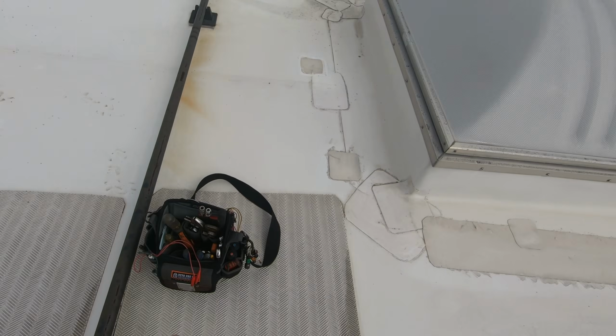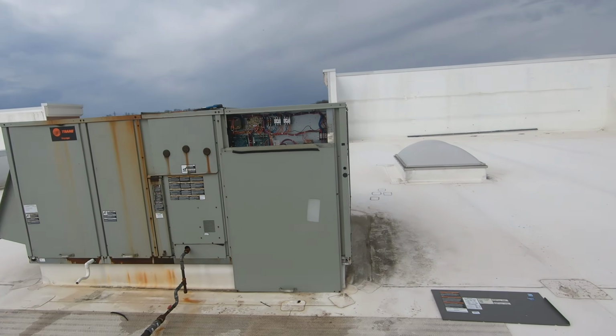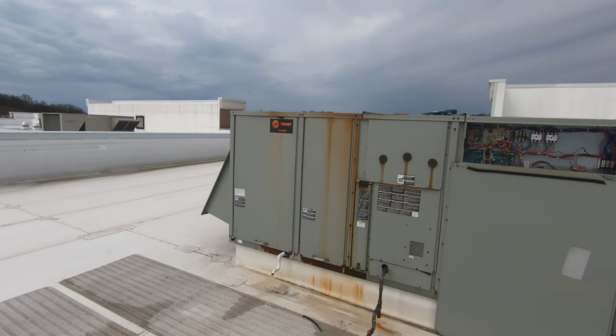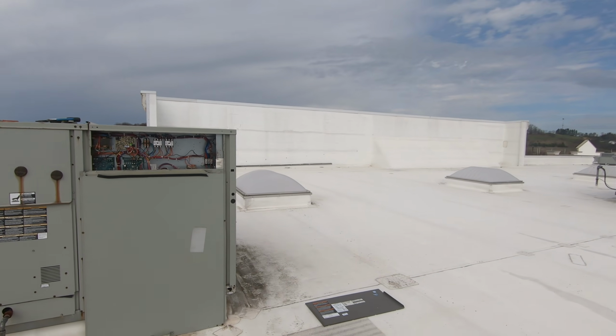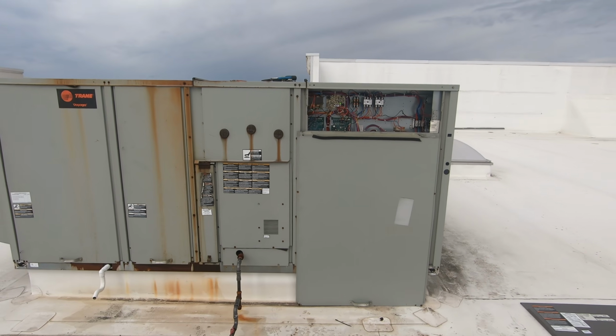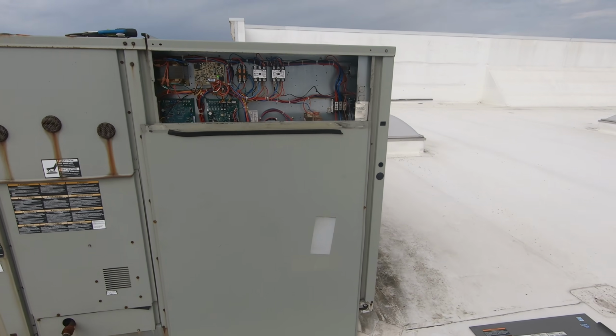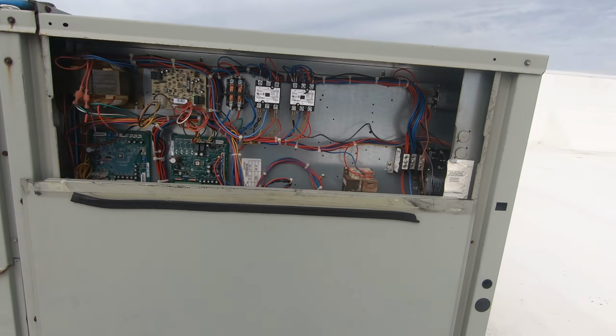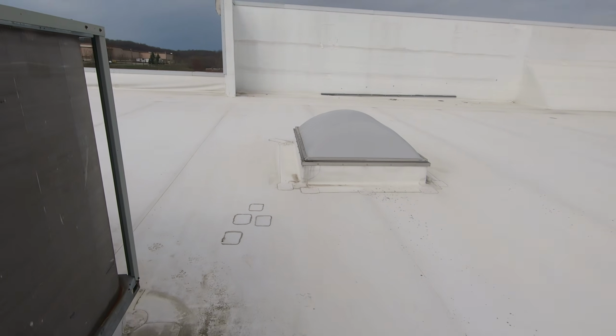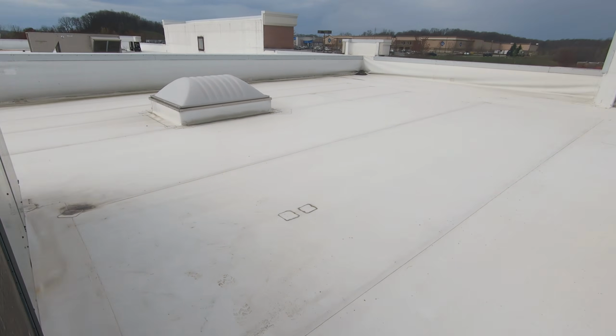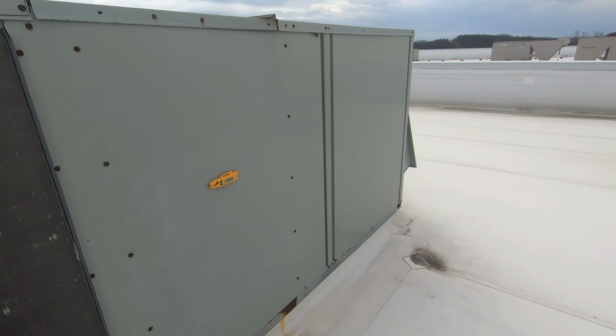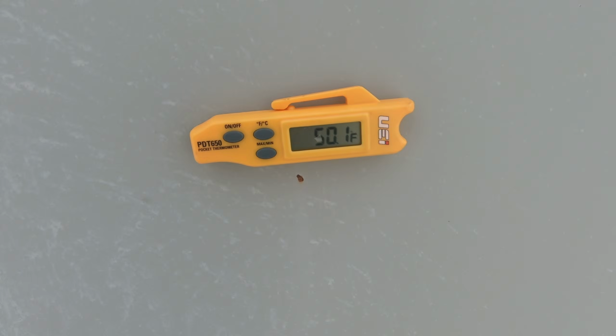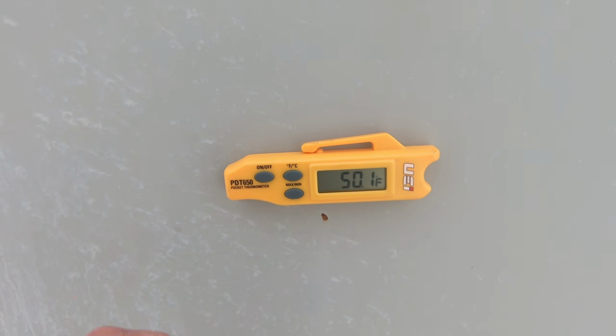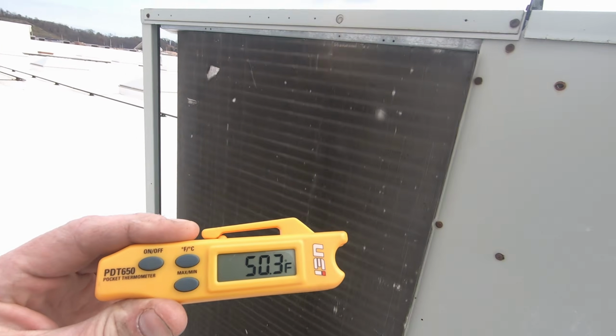So, another easy service call in the books. We do this PM in this account quite regularly. That's why I'm not overly concerned with checking the charge. We've had no issue with it. It's putting out a good supply temp. Suction line's good and cold. My discharge line's good and warm. We've come up a degree or two since second stage kicked off, but we're good to go.